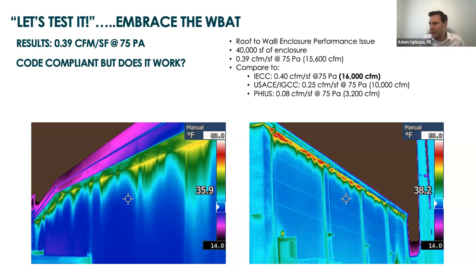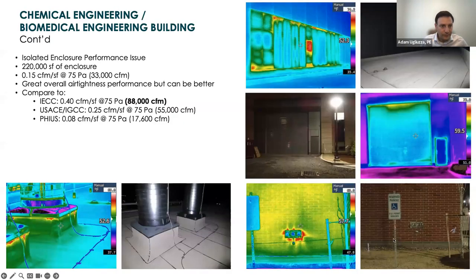As you can see in the IR scans here, this thing had some serious leakage around the perimeter of the building. We were at 16,000 CFM of leakage. If you're going down to PHIUS level, this would never pass. It wouldn't have passed the Army Corps level either, but at code it did. So that's just to give you a frame of reference when you're testing a building for the first time.